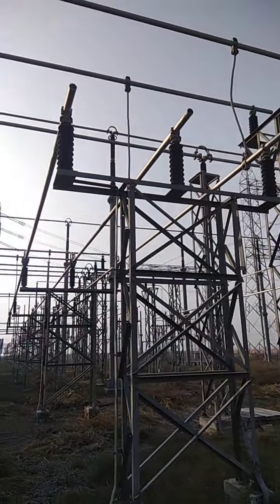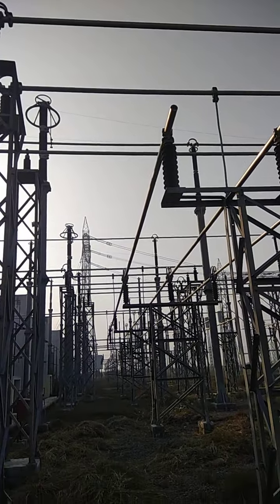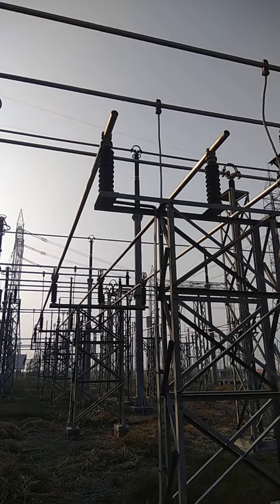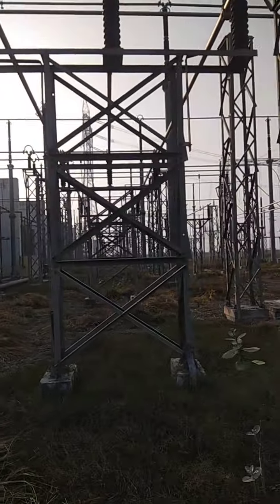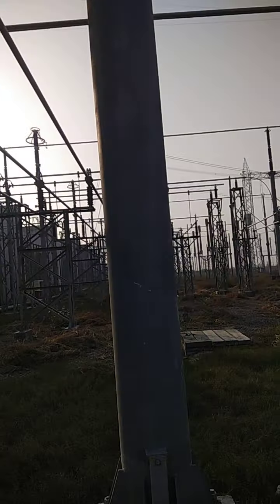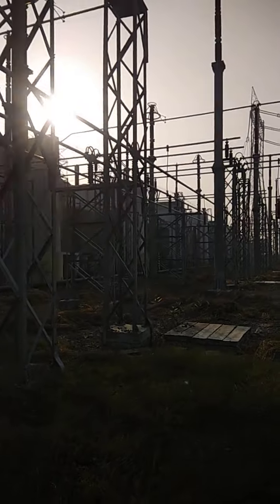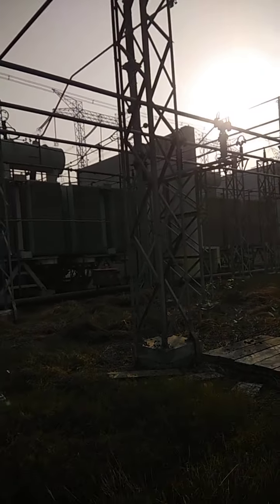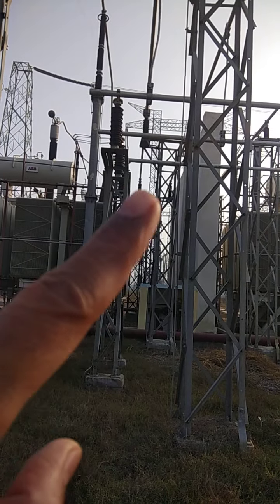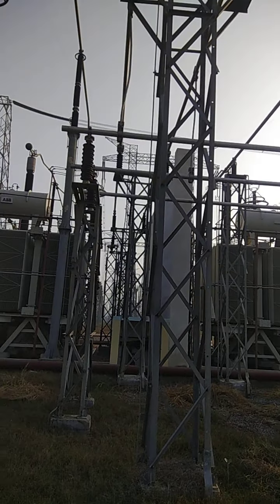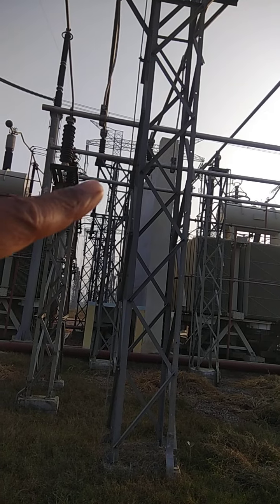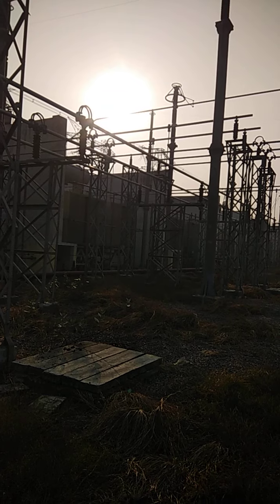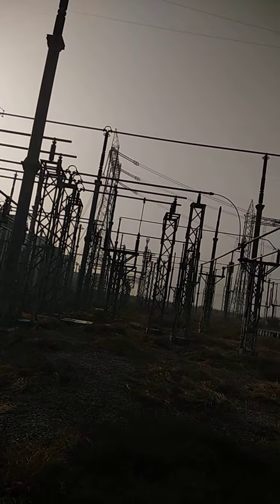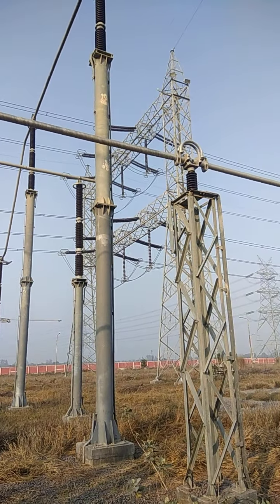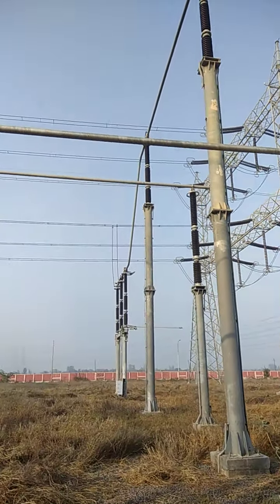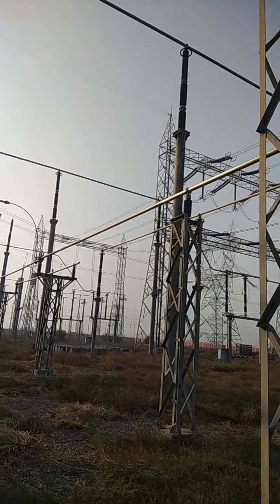We are taking two bus outputs from each unit. You can easily see this is the 33 kV bus arrangement, and this is the lower bus where we made a delta here. For the star arrangement we have made this neutral bus arrangement. All three neutrals are combined on this bus and generate a star point here.